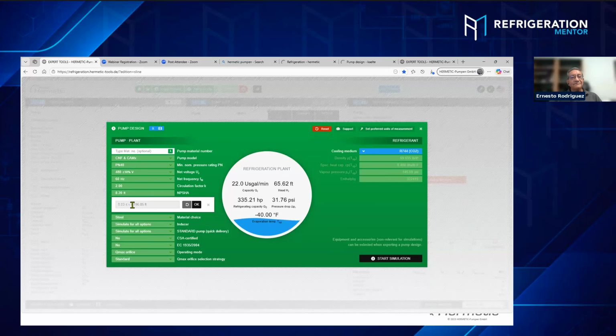So this is something that's really important. A net positive suction head. A lot of people don't know or even check that. What is that, and why is it important when you're dealing with a pump? Well, basically, you need to have a good level of liquid on the suction of the pump. When you start the pump, it's going to start getting fluid from the vessel and prevent cavitation, basically.